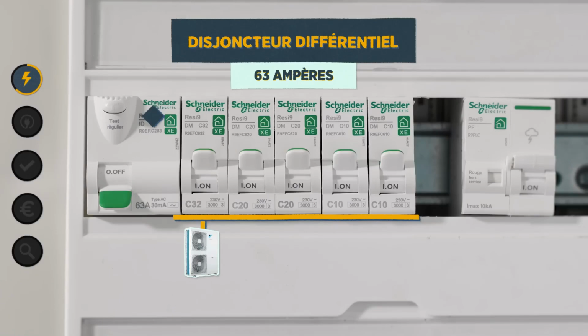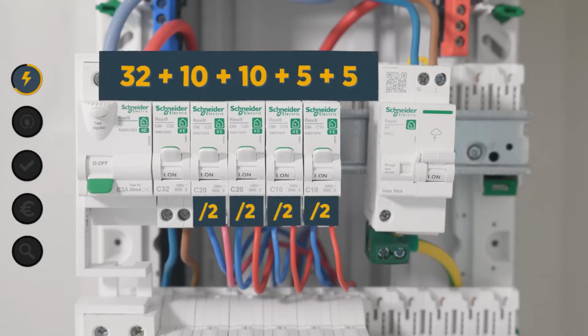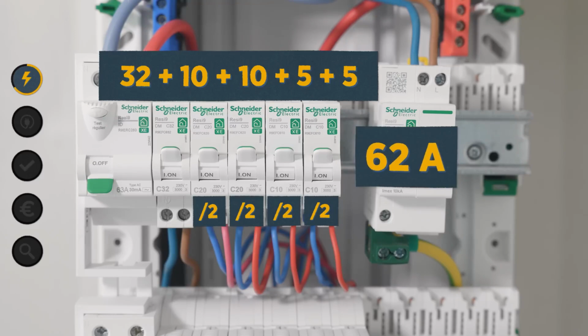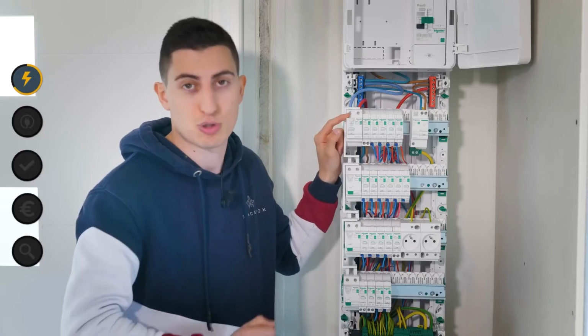Then I have two 20 amp breakers for my outlets, and there we can divide by 2, and two 10 amp breakers for my lights, same there, we can divide by 2. That gives me a total of 62A: 32A plus 10 plus 10 plus 5 plus 5. My differential of 63A is therefore well sized.